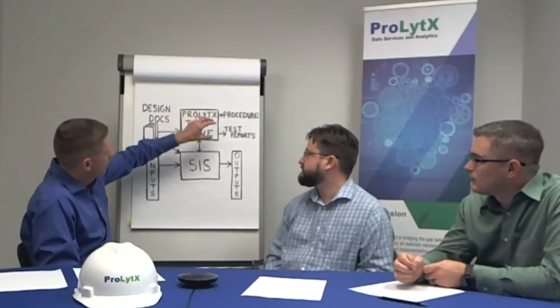Yes. And then, the key thing here, test reports. We had a pain point on documentation of what happened. But here we're actually recording all of the output changes, everything that's happening in that controller, right? So you're able to report that out and validate. When you go back and look at that historically, what are you seeing when you're looking at that report? So you're seeing step by step what was defined for the test procedure. You're seeing what occurred, what you forced into the system, and what the expected results were, and you can see the actual results with actual values. And then in addition to that, you're seeing any steps that you did manually. So if you were to stop the structured test and do something manually in the system, that also gets recorded and embedded within the test log.